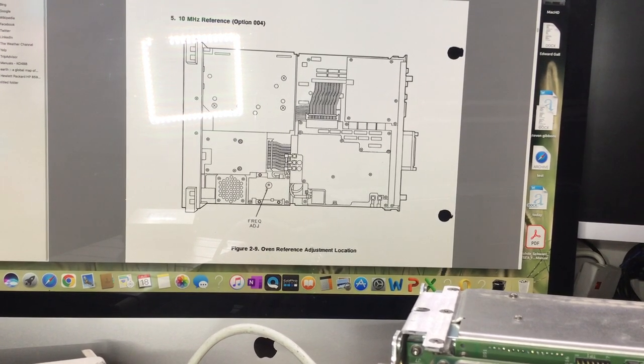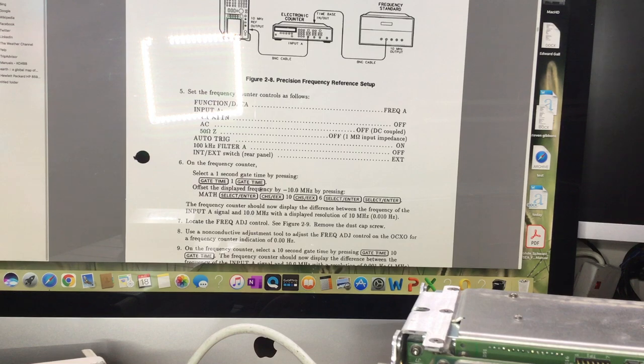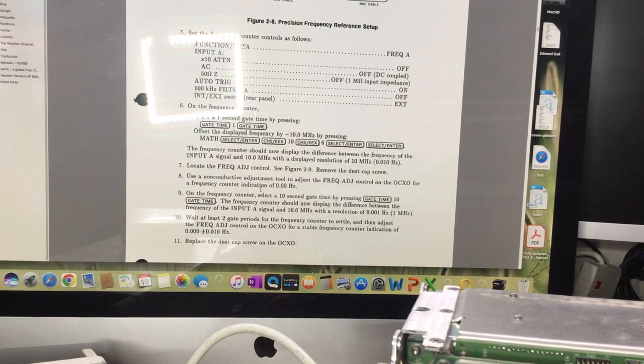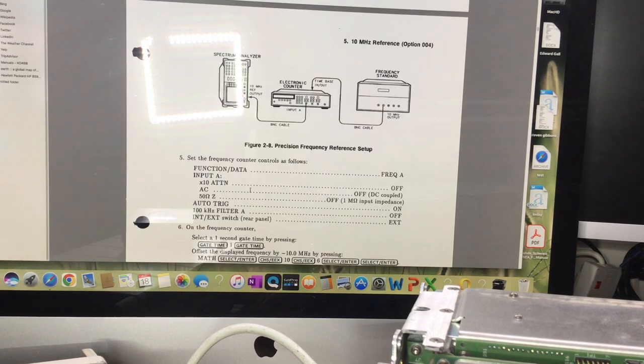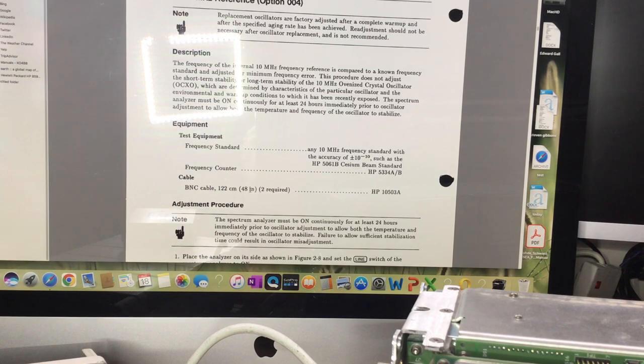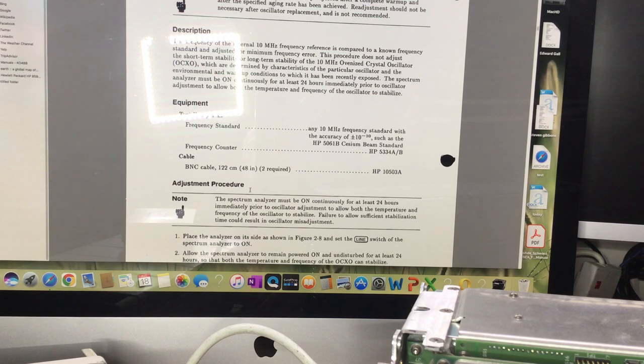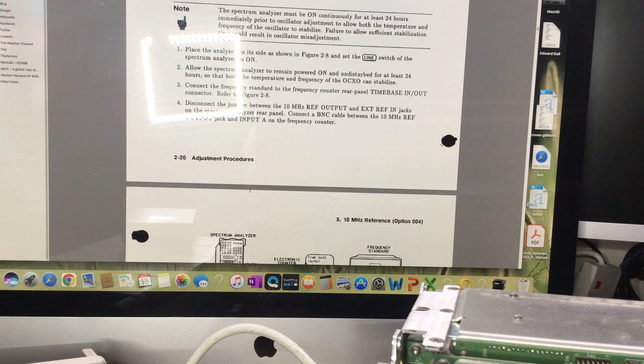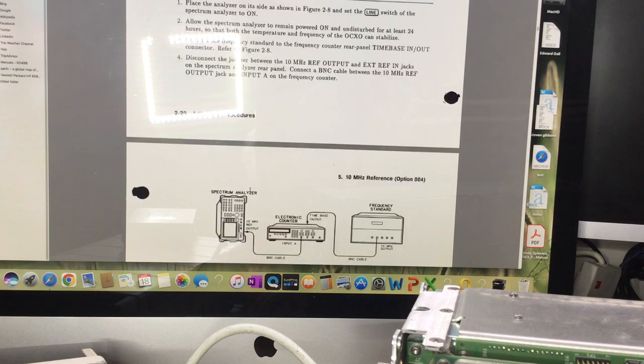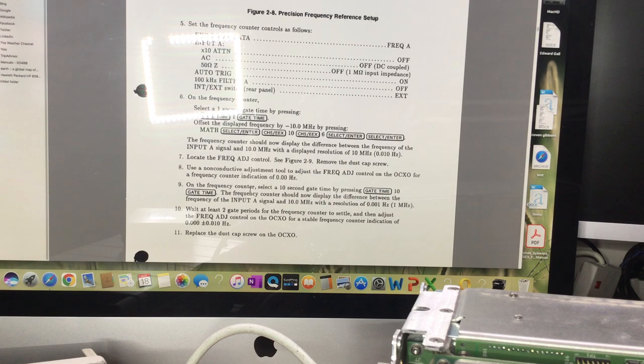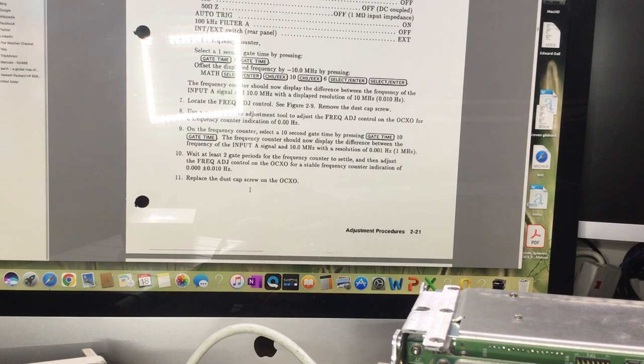According to the service manual, you can either adjust it manually using this frequency adjustment potentiometer, this hole there, which isn't on this particular model, but then of course it talks about adjusting the frequency manually by going into the cal and changing it there. There's some more information here about it. 10 megahertz reference option 4. So it talks about going into the menu.